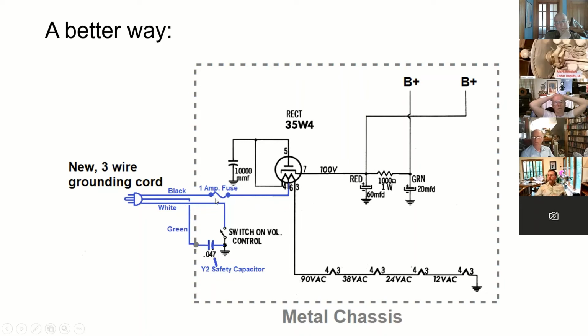But if you put a small fuse in here, like a 1 amp or 2 amp or something like that, that fuse should blow before there's a hell of a lot of damage. And you know, you don't want 12 amps of current flowing through there, and it's just not enough to trip a 15 amp circuit breaker. So the best way is to put a 3-wire cord and a fuse that goes before anything, before a switch, before anything.